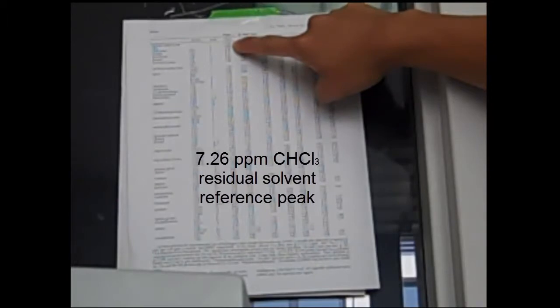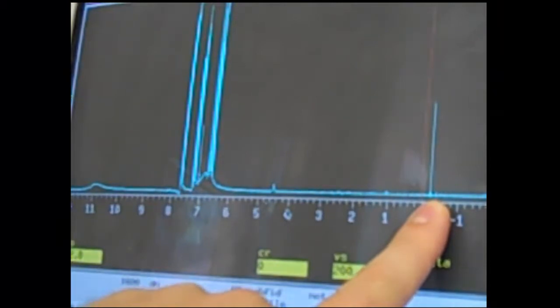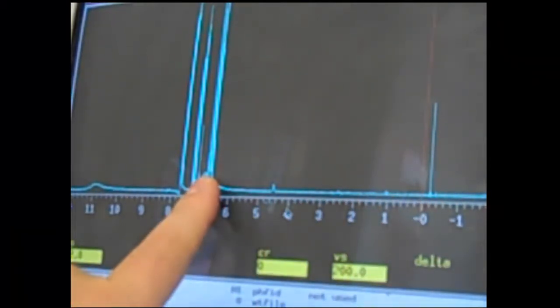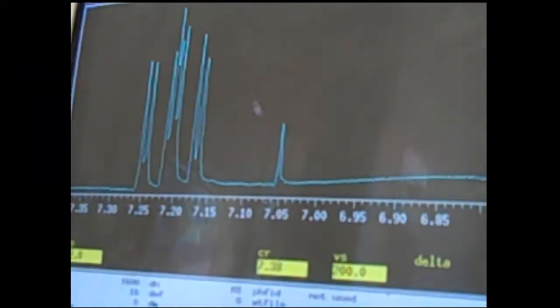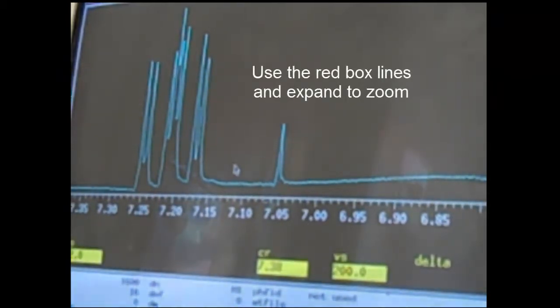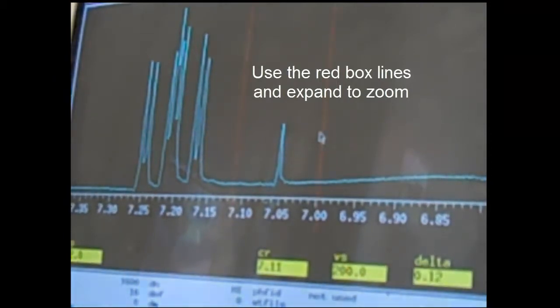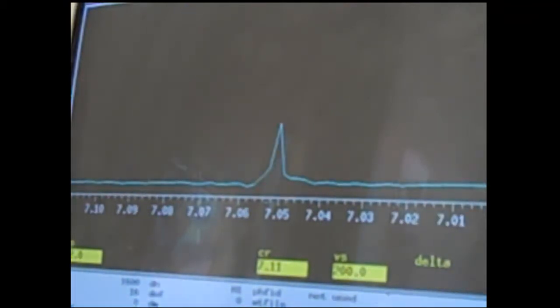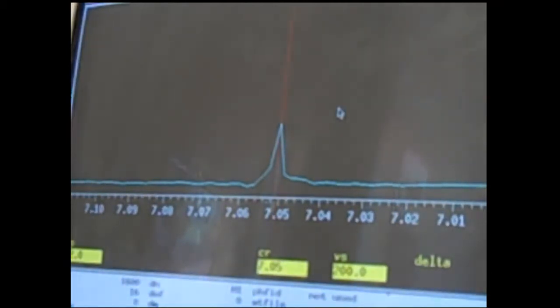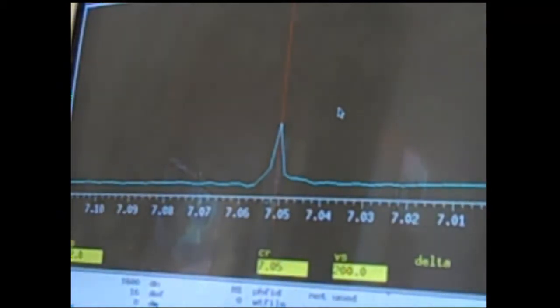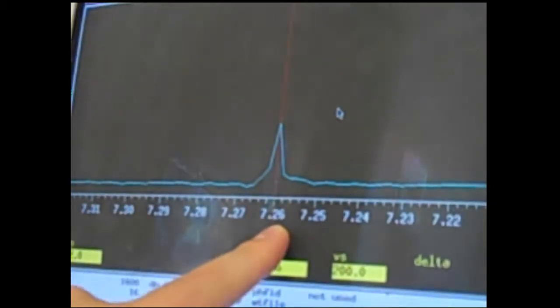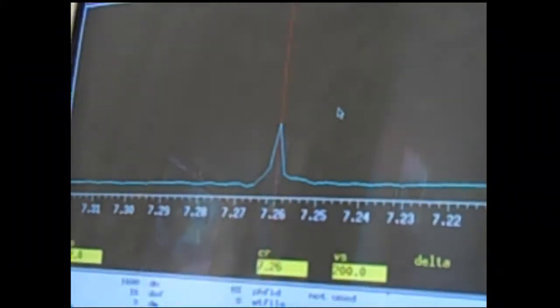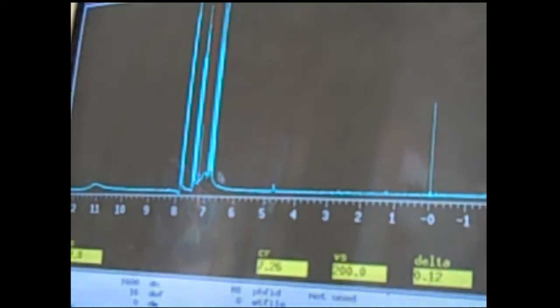We can see the TMS peak here at zero, but ideally I'd like to reference the solvent peak around 7.26. So here's our solvent. Oftentimes it will show up just a little bit low. If I want to zoom in, I can left-click, and you'll notice the red line here, right-click, and then up in the menu I'll click on Expand. That zooms in on that peak. If I left-click in the center of the peak, and then up in the cursor box type in RL, meaning reference line, parentheses 7.26P, then notice it'll reference that specific peak at 7.26. Now we should see our TMS peak right at zero, which it is, and then our solvent peak should be right here at 7.26.